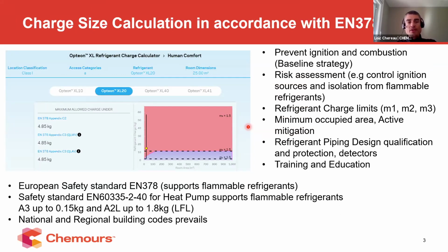conditions and standards that need to be followed by the OEMs, to make sure these OEMs can use the refrigerants in a correct way, depending on the charge size, of course, the location where the heat pump will be used, be it for instance installed on the floor, on the ceiling, on the wall, but also different types of room. So the dimensions of the room is also something to consider, to make sure all this equipment will comply with the EN standard, be it the EN 378, but also the EN 60335-2-40, which is applicable for the heat pumps and for the appliances.